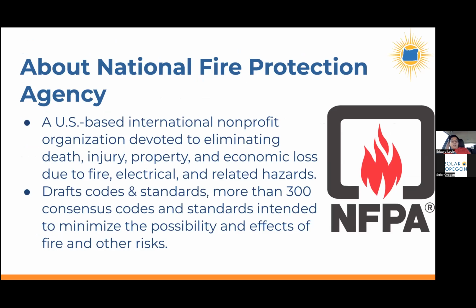NFPA is an organization that is closer to how you take those UL tests and how that applies to actual rules pertaining to the placement of batteries in the home. Like, can you put them in the garage, or do you have to put them outside? For example, the 3-foot separation rule, that's actually an NFPA rule. How NFPA decided on the 3 feet separation is that they looked at the test data from the UL test reports, and they're like, okay, we've read a dozen of these reports now, and we watched a video of how the flames propagate or don't propagate. And so we're going to set 3 feet as the number that we think is appropriate, so that if one module catches on fire, the flames won't be close enough to catch the other module on fire.